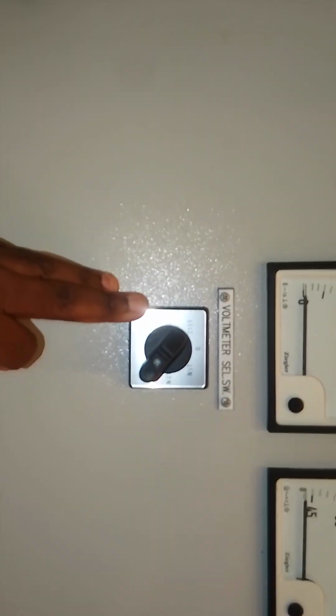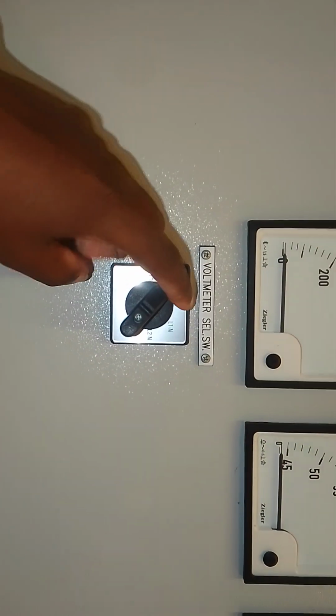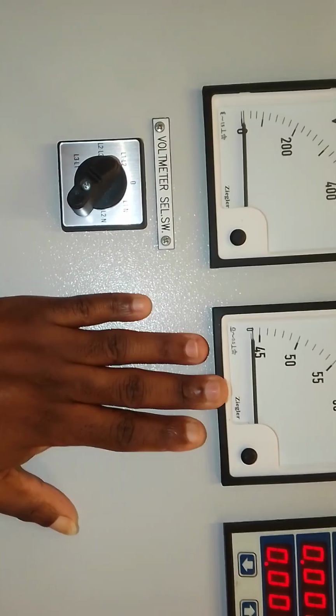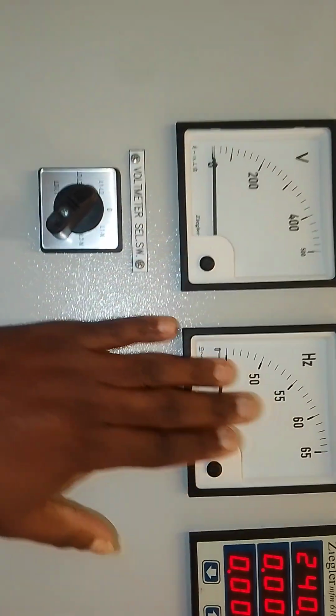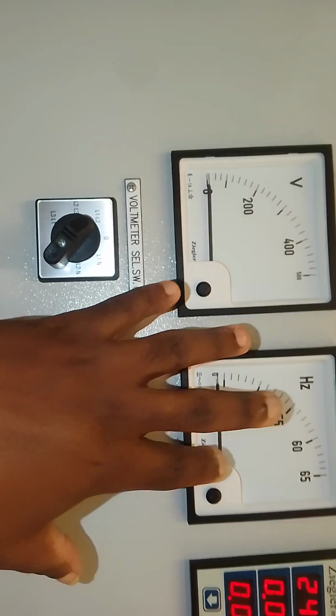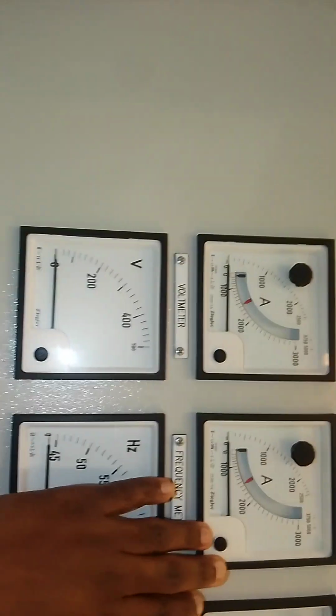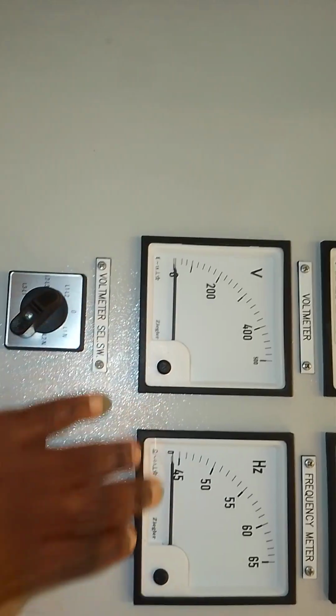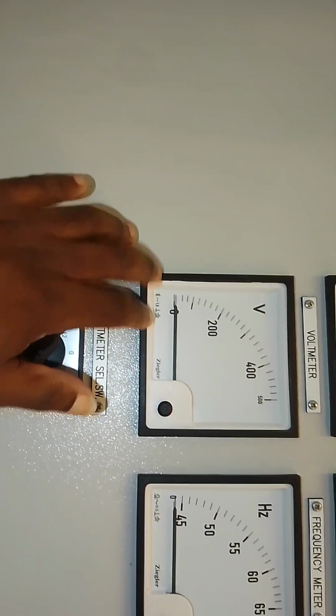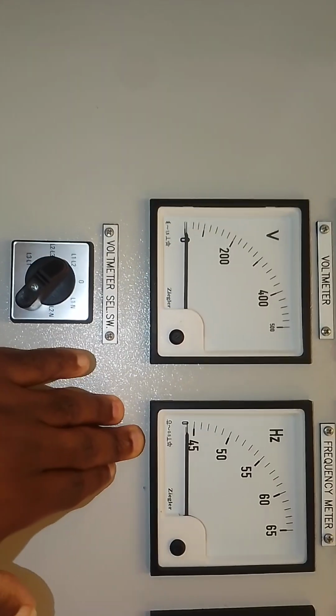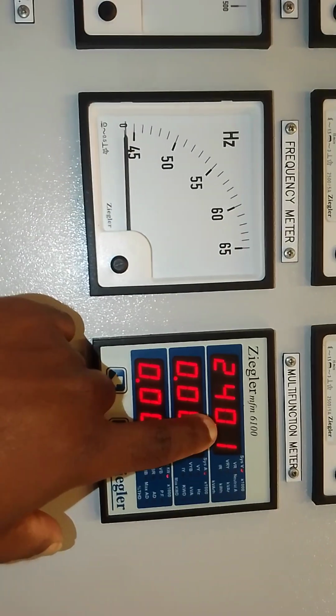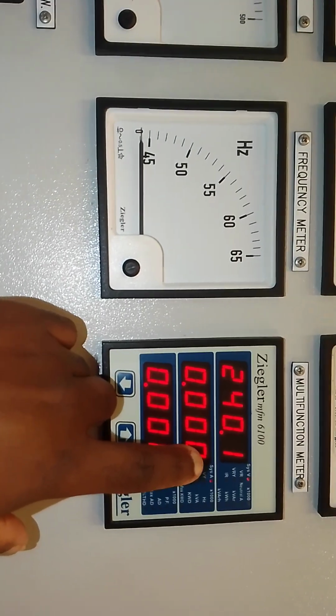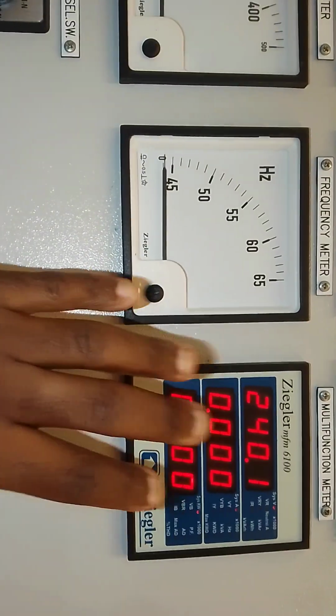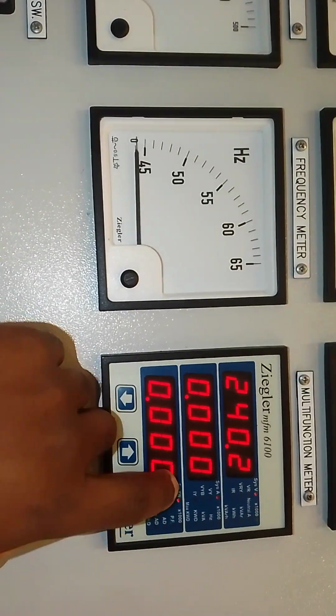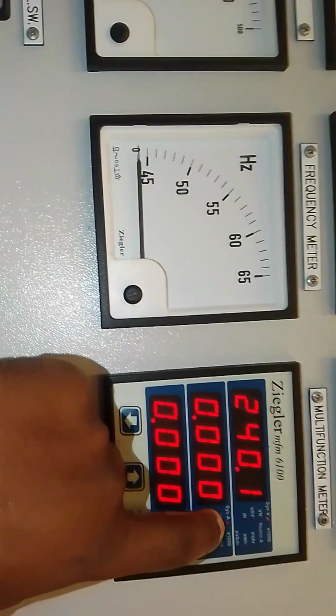Also we have this selector switch for checking voltmeter. We have ammeter, which is showing you the ammeters are off already. You can see also voltmeter is off. It is not off, but it has no any volt because already the generator is off. This power which is showing here is just for operating the ACB. Otherwise there is no anything else going on. You can see showing you the kilowatts is 0 and current is 0.